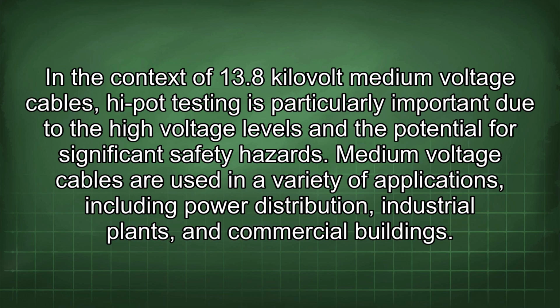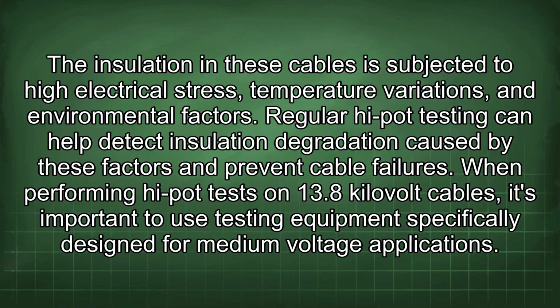In the context of 13.8 kV medium voltage cables, hi-pot testing is particularly important due to the high voltage levels and the potential for significant safety hazards. Medium voltage cables are used in a variety of applications, including power distribution, industrial plants, and commercial buildings. The insulation in these cables is subjected to high electrical stress, temperature variations, and environmental factors. Regular hi-pot testing can help detect insulation degradation caused by these factors and prevent cable failures.